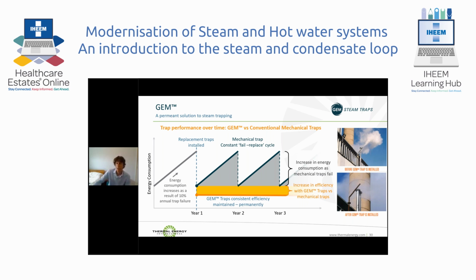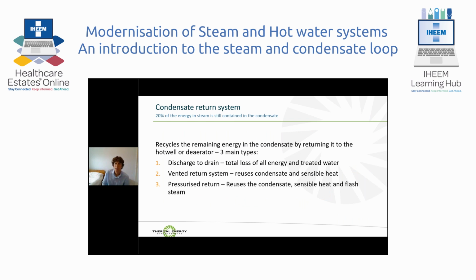We now move on to the condensate return system. Once we've condensed the steam into hot water, 20% of the energy is still contained in the condensate. Roughly half of that is lost as we release that 180 degree condensate across the steam trap, and a portion of it re-evaporates.